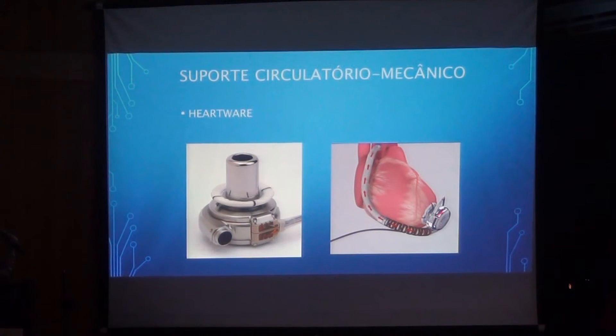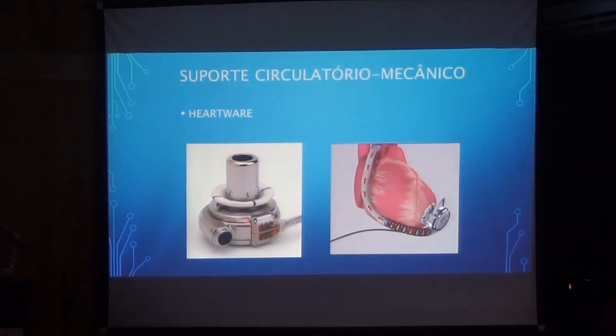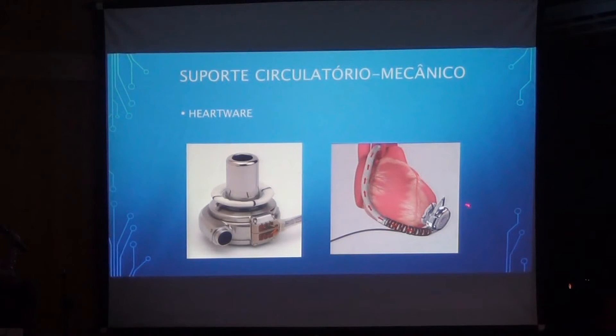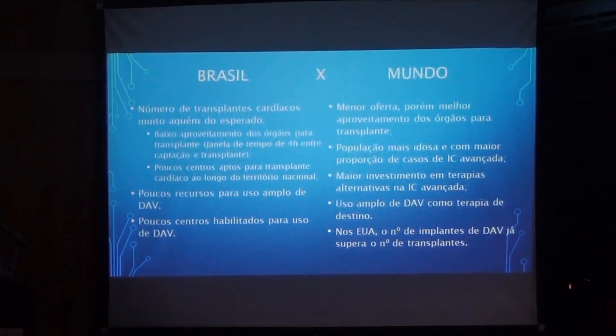Finally, the HVAD — a centrifugal pump that is quite small and interesting. It is mainly used in patients with a smaller body type, such as women, who cannot accommodate a larger device in the thorax. It also cannulates the left ventricular apex and returns flow to the aorta, with a much thinner driveline. It is a more modern device.